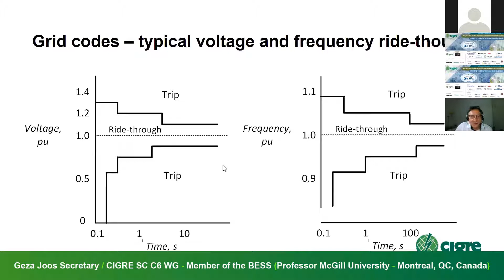For example, in Quebec, the low voltage ride-through has to be at least 5 cycles and 0 volts, which is an extremely stringent requirement, which means essentially that the inverter has to be configured in such a way that it keeps a reference voltage for the duration of the 0 volts. So you do it through the PLL, you freeze the PLL to the previous value, hoping that when the grid comes back, you come back at the proper phase angle. Frequency ride-through, again, depends upon the utility. In Quebec, we have very wide frequency ranges because it's an isolated system.